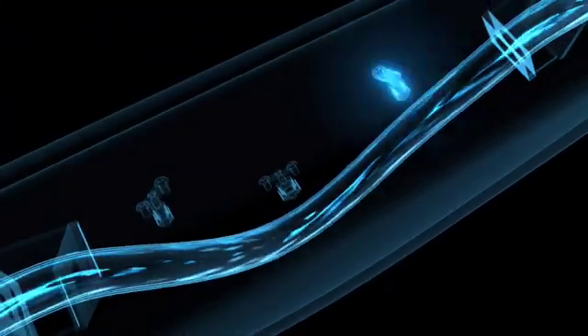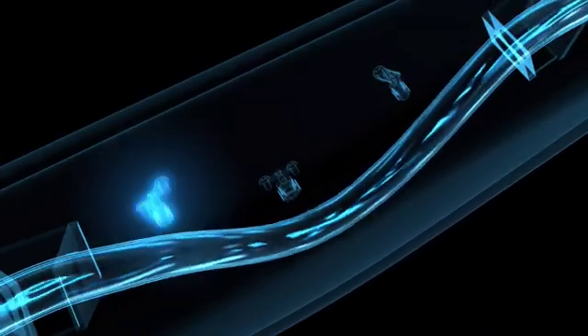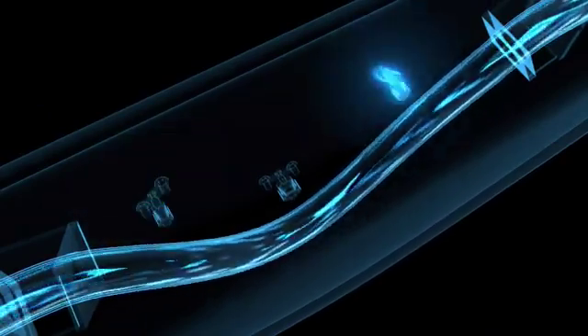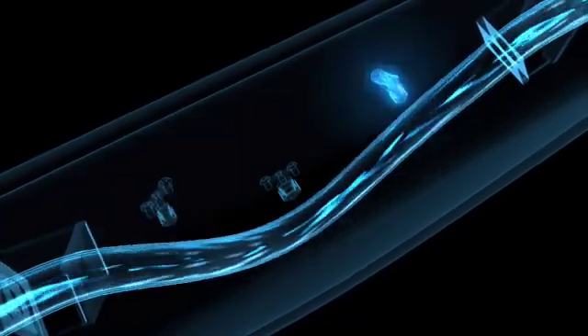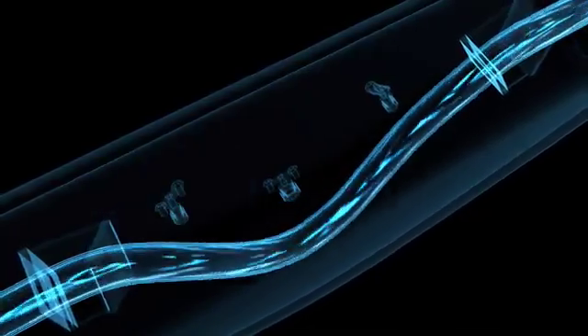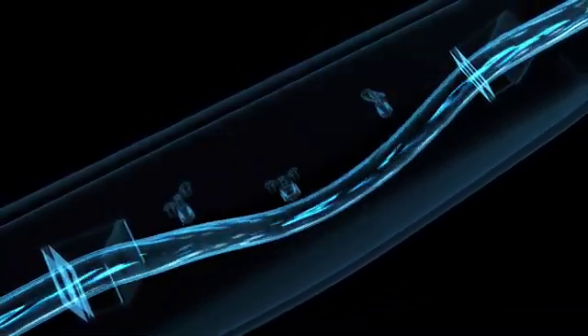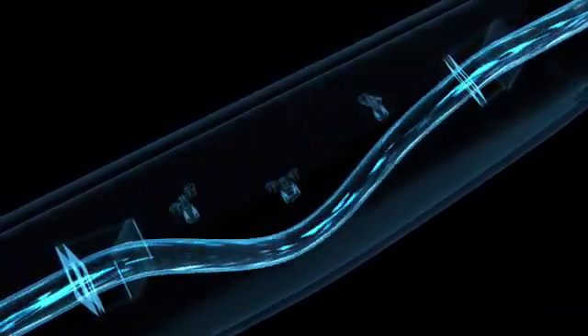This is known as the phase shift and is a direct measure of how much liquid or gas is currently flowing through the pipe. The higher the flow velocity and thus the total flow, the greater the deflection of the oscillating measuring tube.